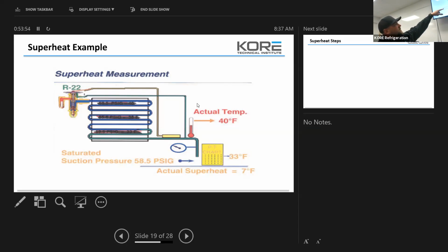So you've got your pressure, you have your pressure stubby. You can do stubbies, or if you're on a market, I'm okay with you using charging hoses. I like stubbies. They're nice. They're easy. You can carry them everywhere. If you got a pair of Bluetooth gauges, Bluetooth's nice. Thing about Bluetooth gauges is you can hook up to that, and you can hook up your clamp to the pipe, and you can tell the app what the refrigerant is, and it'll tell you what the superheat's supposed to be. But if you don't have that stuff, all you guys should have a PT chart somewhere in your truck. If not, you have an app on your phone. There's like 10 of them out there that are PT charts for any refrigerant you're dealing with.